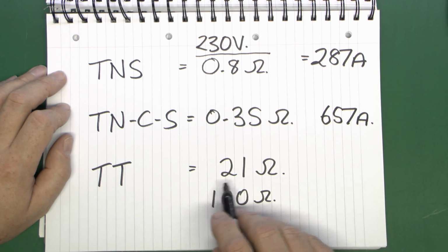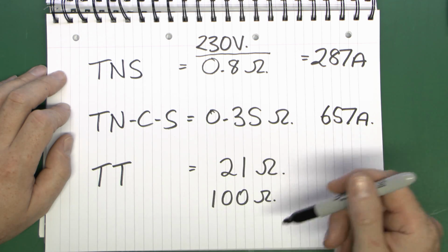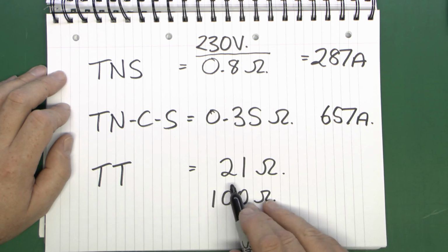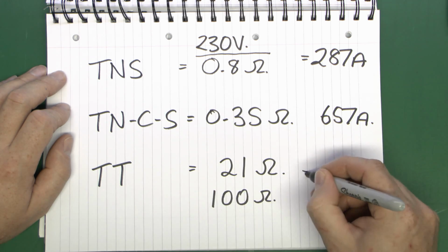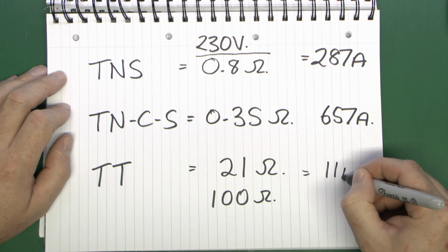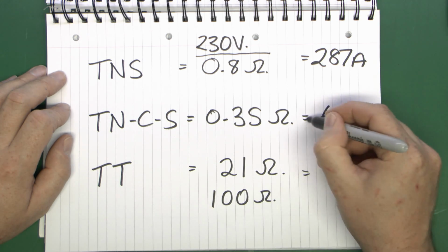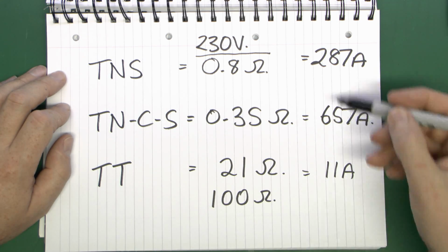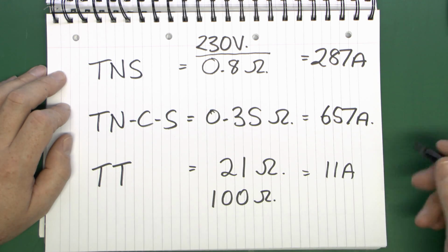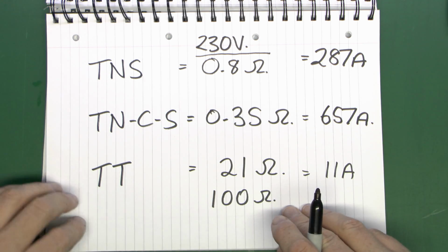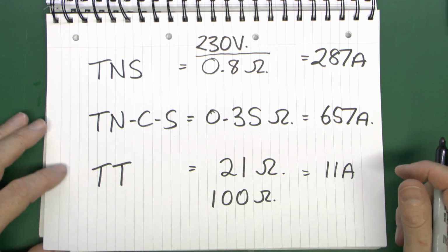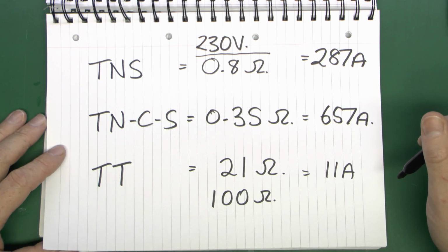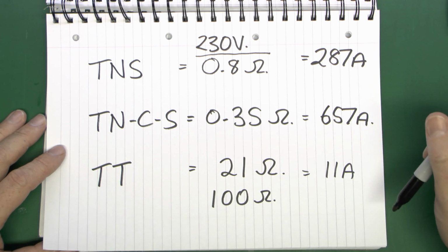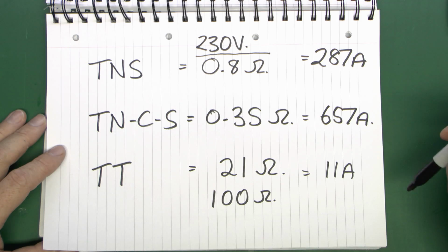And then for the TT supply, it's going to be much, much smaller. So 230, we'll use the 21 ohm value here. 230 divided by 21 would give us a total current flowing of 11 amps. So why are these actually particularly important and why would we really care? Well, the answer is that in any kind of circuit, you're going to have a protective device, typically a fuse or circuit breaker or something. And in order for that circuit breaker or fuse to actually trip when there's a short circuit fault, it needs a certain amount of current to flow through it.